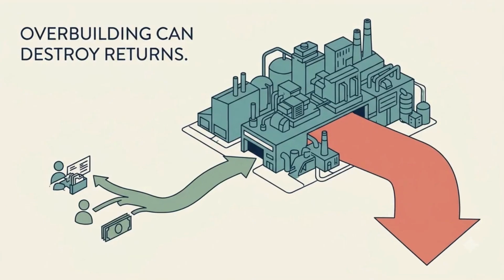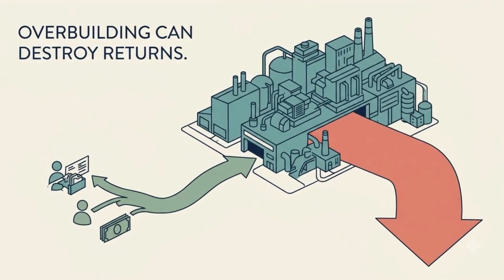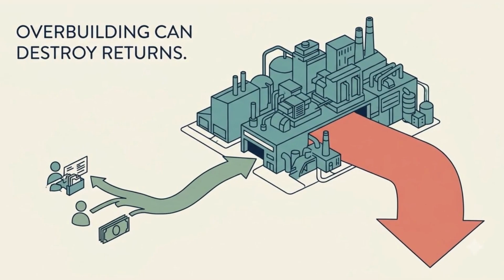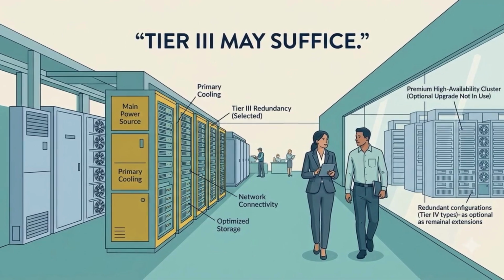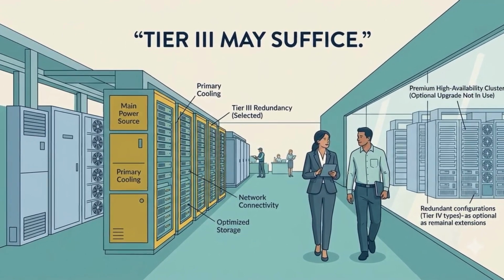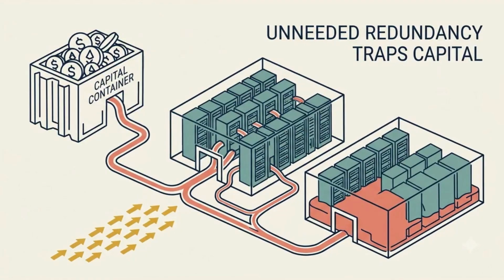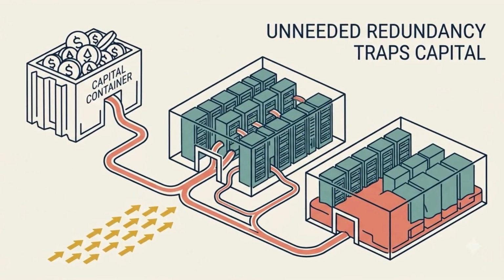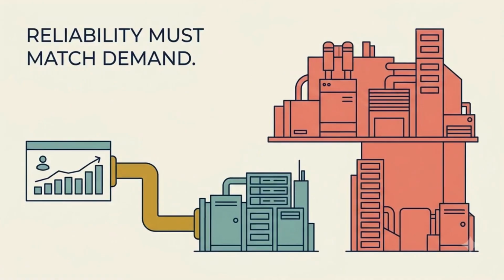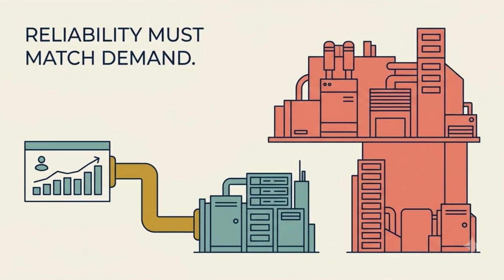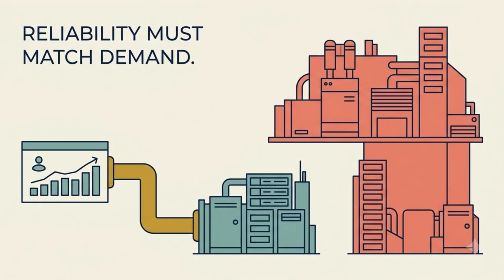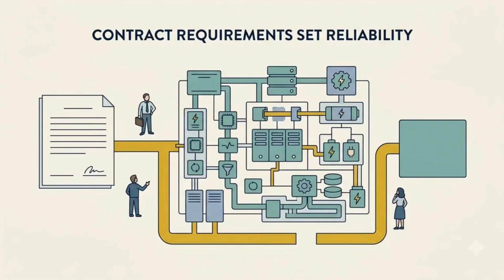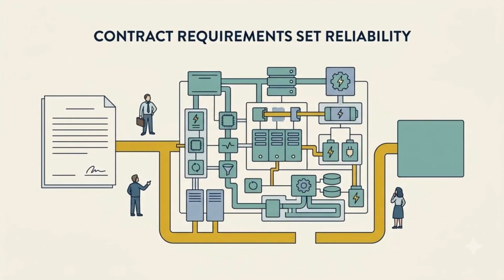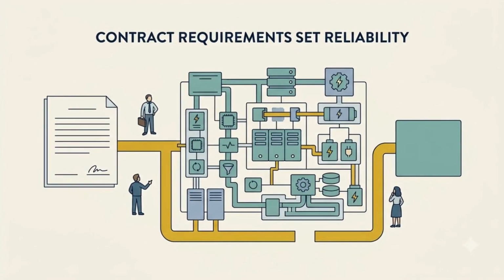It is whether customers will pay enough for it. Overbuilding can be as damaging as underbuilding. If a market mostly accepts a well-designed Tier 3 type environment, spending far more to chase a level of redundancy that tenants do not value can trap capital inside equipment that does not produce proportional revenue. Reliability should be matched to customer demand and contract requirements, not to the owner's desire for the most expensive badge.